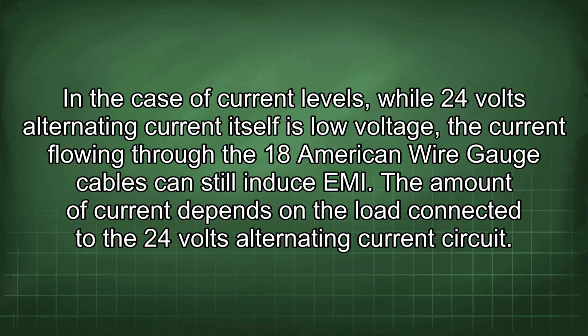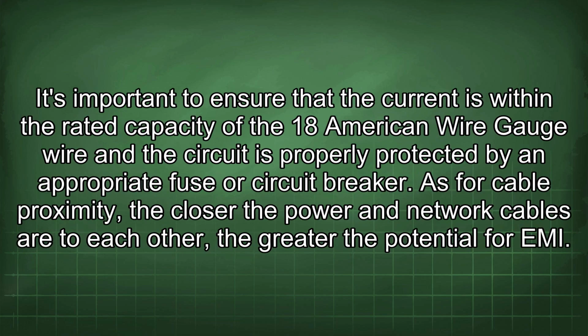The amount of current depends on the load connected to the 24 volts alternating current circuit. It's important to ensure that the current is within the rated capacity of the 18 American wire gauge wire and the circuit is properly protected by an appropriate fuse or circuit breaker.